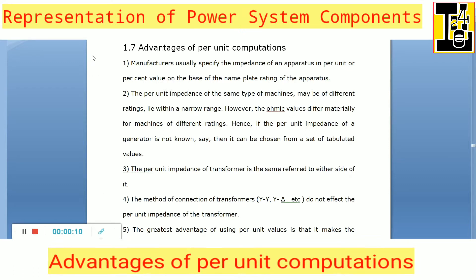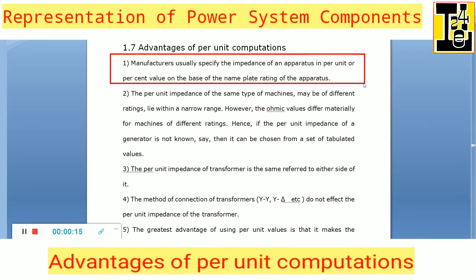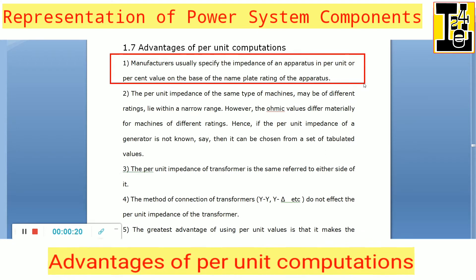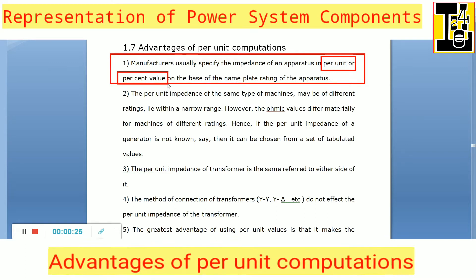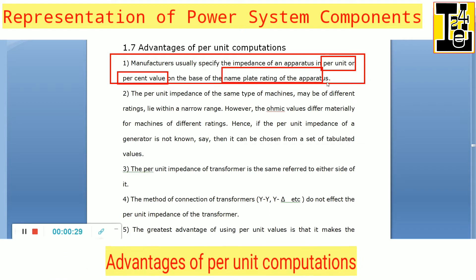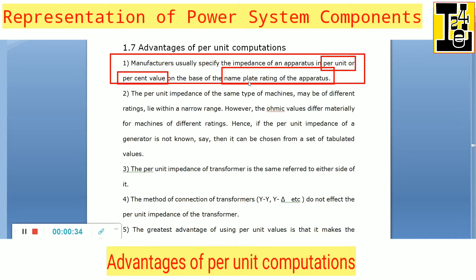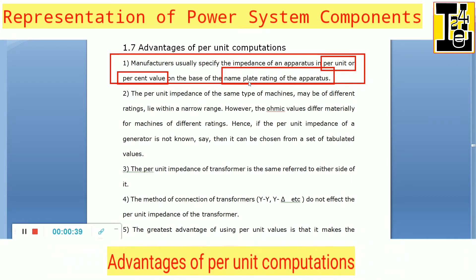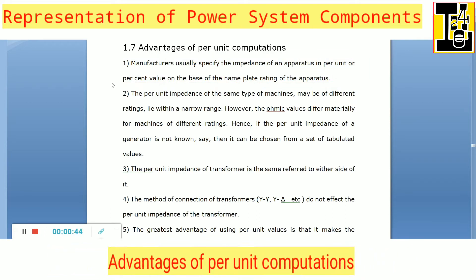The first advantage is that manufacturers usually specify the impedance of an apparatus in per unit or percentage value on the base of the nameplate rating of the apparatus. So based on the nameplate rating, the impedance or reactance of an apparatus in per unit or percentage value is mentioned.